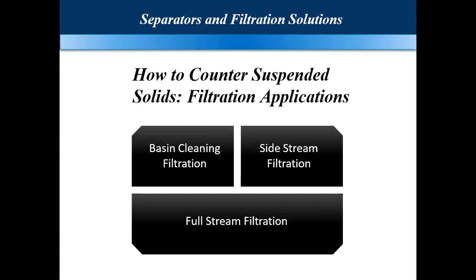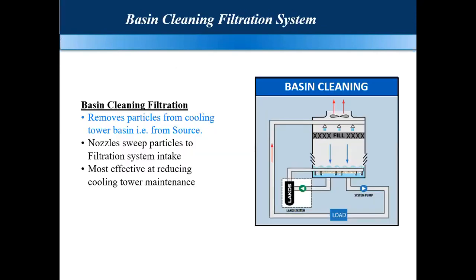The calcium carbonate scaling which is being deposited in your system, if it finds sand or silt coming through the cooling tower, that calcium carbonate and the sand mix together and form a gypsum sort of solution, which will clog your condenser tubes and fills. So we sometimes see concrete-type structures in the cooling tower fills or in the condenser tube, which need to be jet washed after a year or so, or the fills need to be changed. That is because your scaling plus suspended solids mix and form heavy-duty concrete-type structures. So not only treatment, we need to take care of filtration.